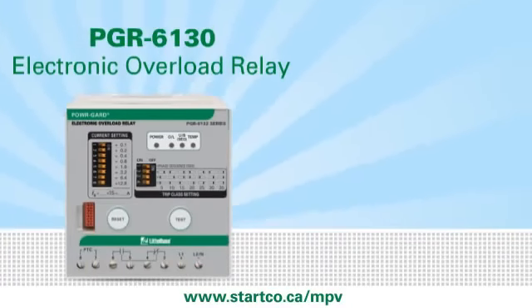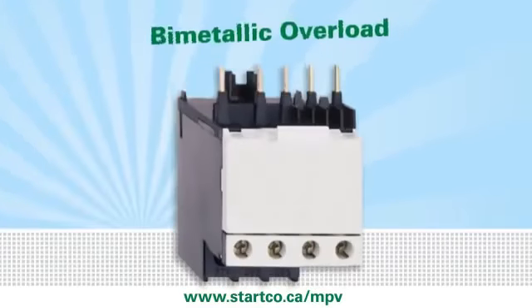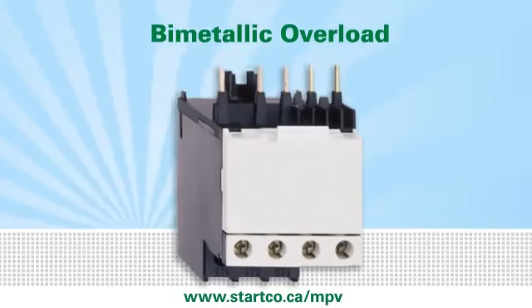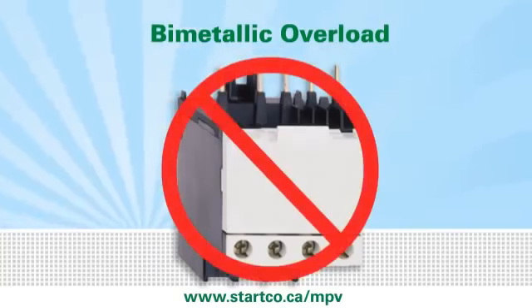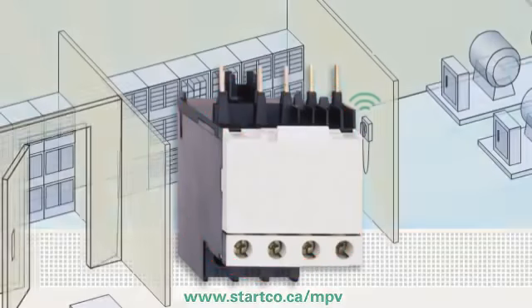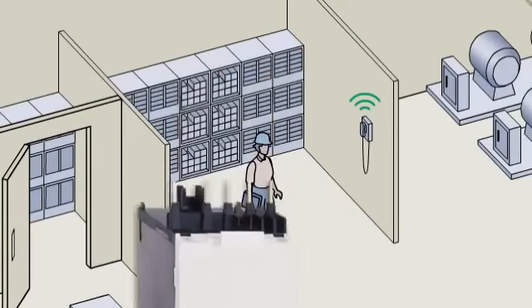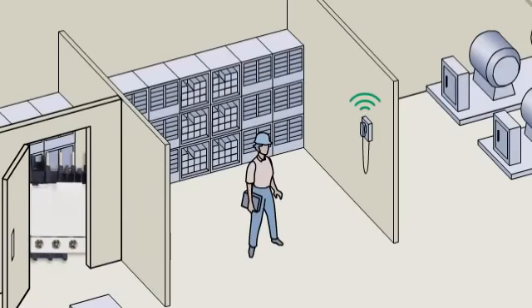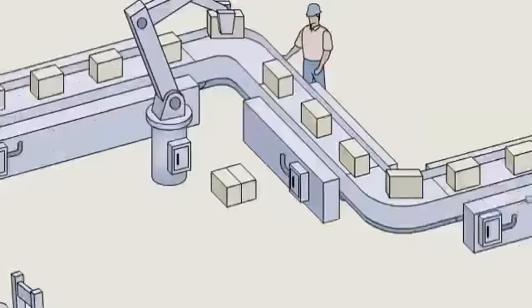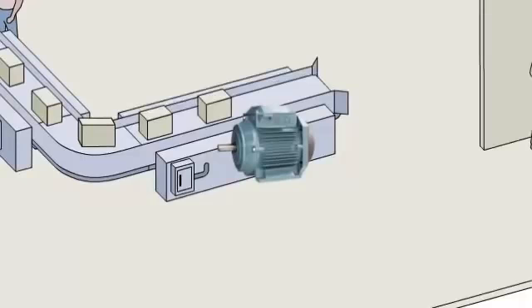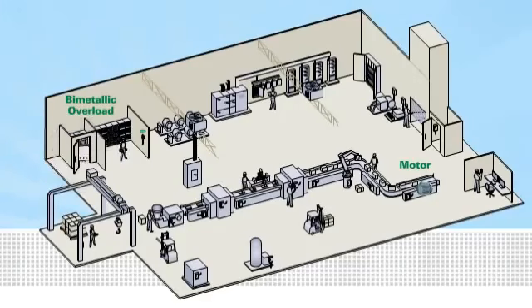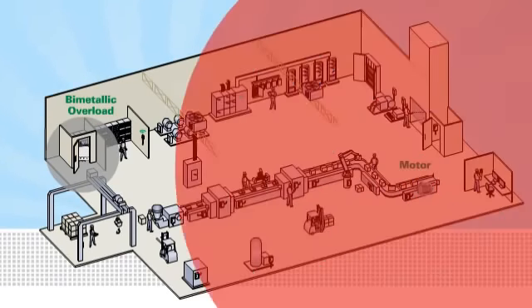or crane controls. You may be using older bimetallic or melted alloy overloads, but this protection is not optimal for today's facilities. These devices are designed to mimic the motor's heating characteristics, which would work if the bimetallic overload is installed in the same ambient temperature as the motor it protects. But in practice, the device is in the motor starter, usually located in an air-conditioned switchgear room. In these situations, the thermal overload can reset prematurely, causing motor overheating and damage.